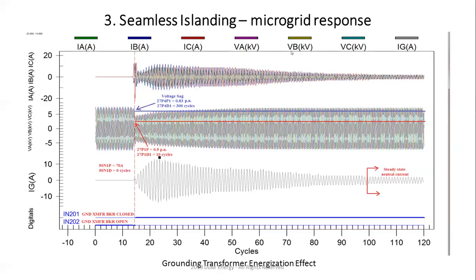So what happens? Well, this is what happens, right? This is just one of those, and there are many of those. Depending on where you switch and how you switch three-phase, and I have a section later on to talk about it, you can have this voltage sag really, really small or really, really large. So this is just one of those. This is what happens in the grounding transformer when you try to energize it, right? The top line shows all three phases, IA, IB, and IC. The second one shows the voltages, and the bottom shows the inrush current into the grounding transformer, between the neutral and ground.